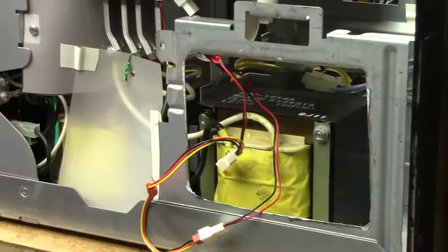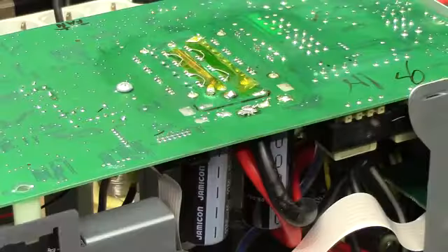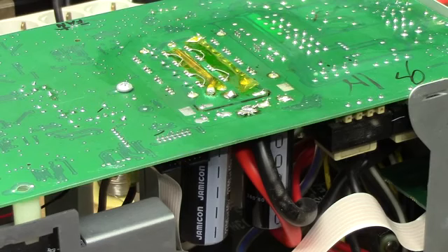And right there you have pretty much the majority of this trick. It's got another transformer installed in the battery compartment. So the gist of the wiring of these transformers is very simple. Their primaries, i.e. the low voltage side, are connected up in parallel, and the outputs are simply connected up in series to provide twice the amount of winding ratio on the secondary as opposed to the normal UPS. So for 12 volts in, you're able to get about 230 volts out.